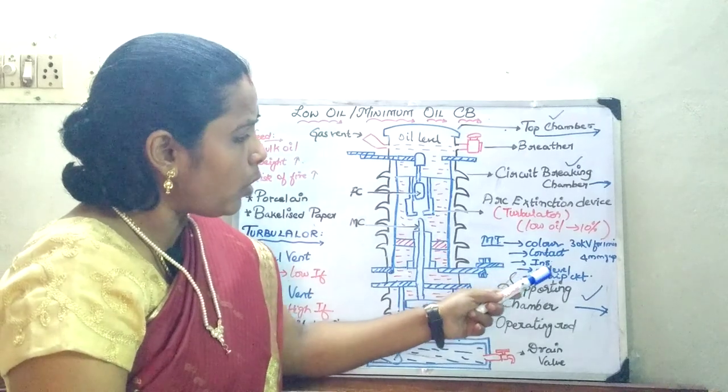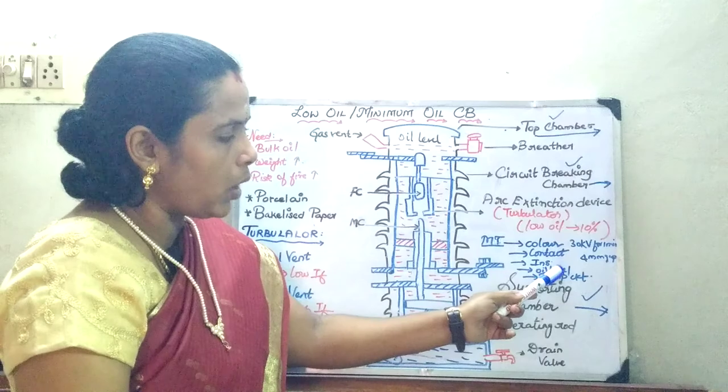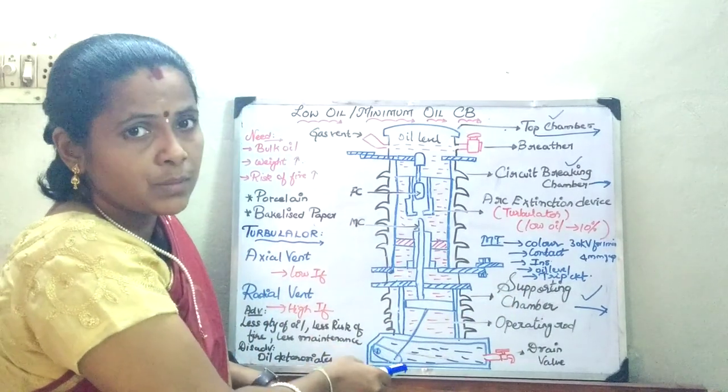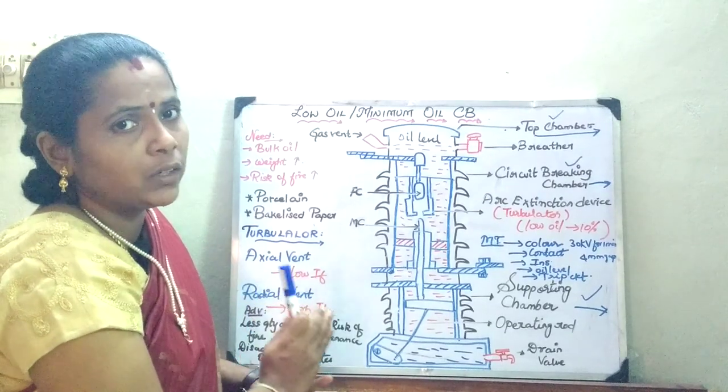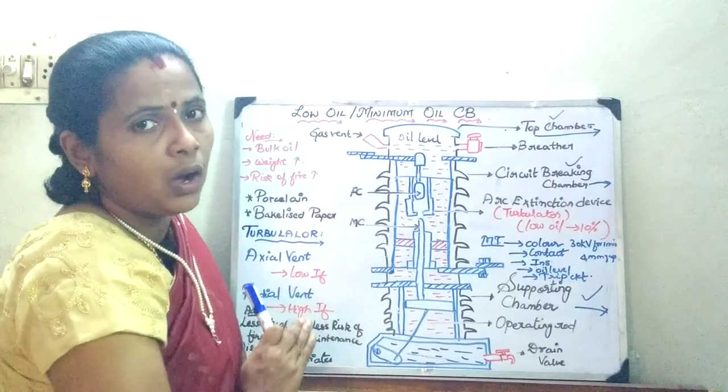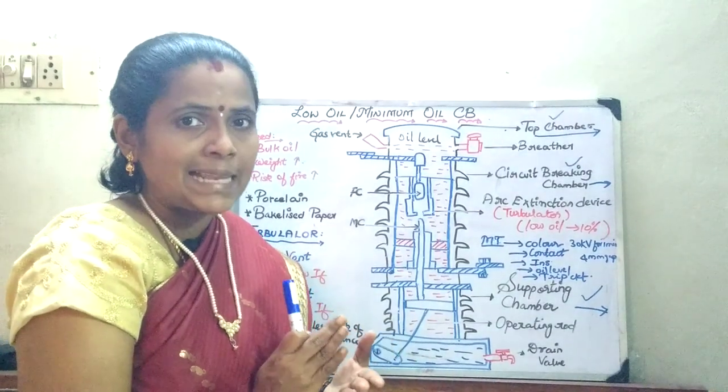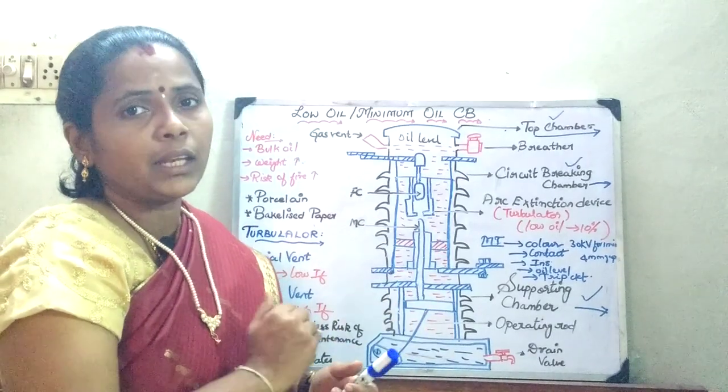Now you have to also check the outer insulation. Then and there you have to check the oil level also, and you should also take care of the other dripping mechanisms associated with it. So the maintenance is quite costly in case of oil circuit breaker. But the main advantage is that it uses less amount of oil and less risk of fire.